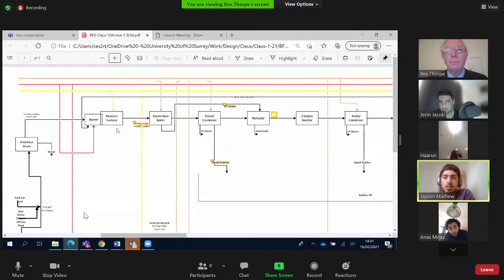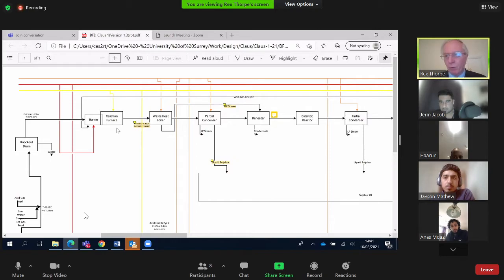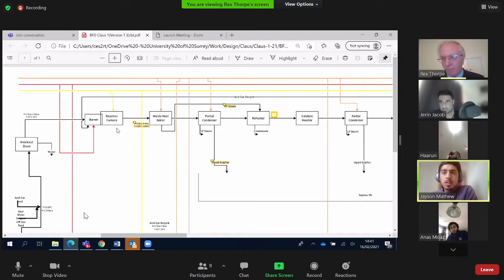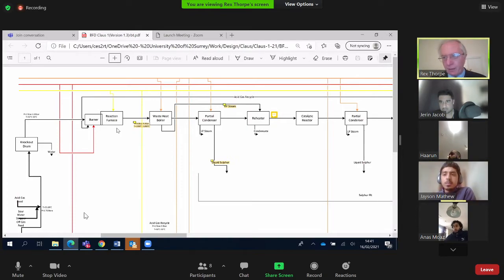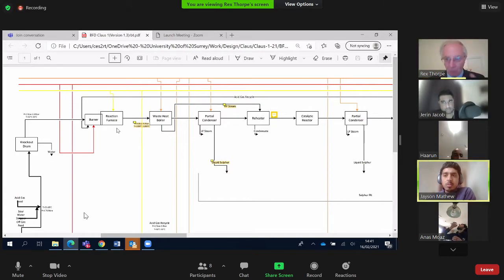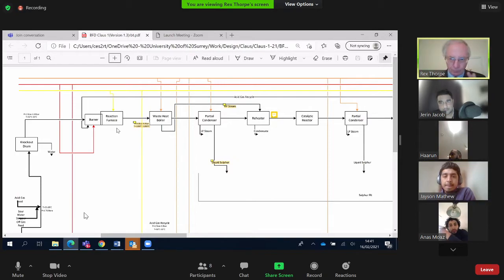Condensate, sorry? Well, no, because you're not putting steam in. You can only get condensate if you put steam in. What normally when people say condensate, it's for steam, steam condensate, which is water, quite pure water, so you return it. You only get condensate if you put steam in, and steam doesn't mix with something else, otherwise you'll get contaminated stuff.